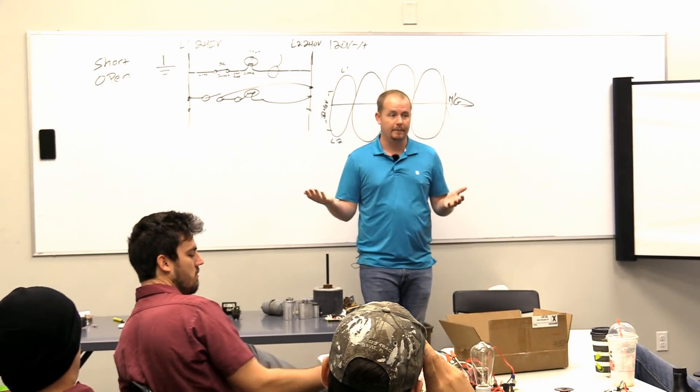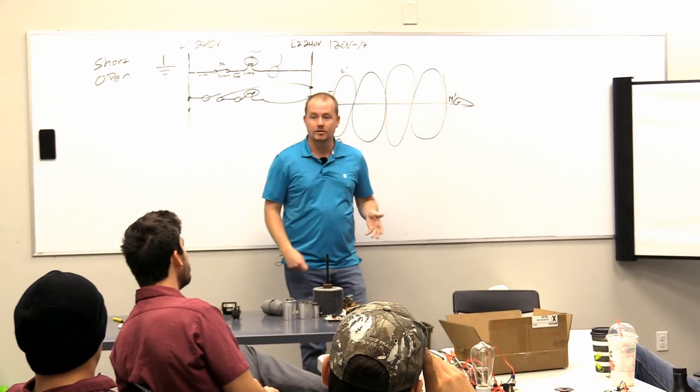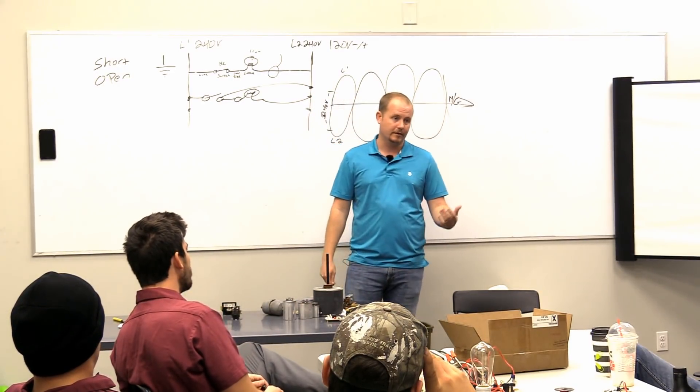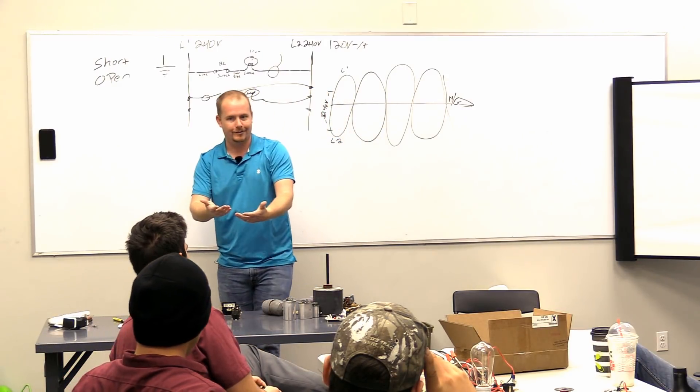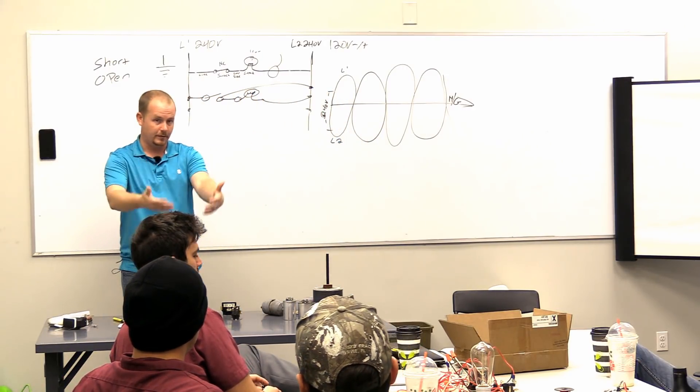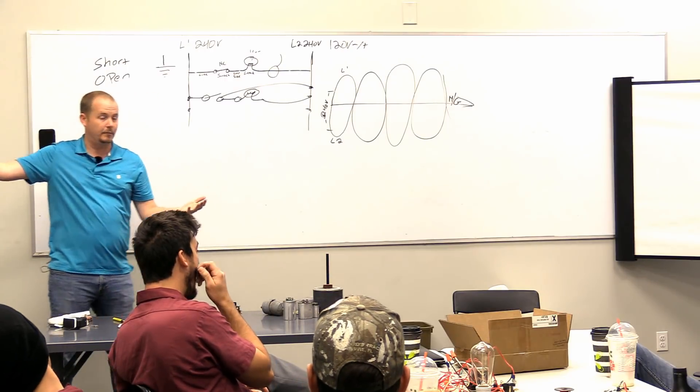And we see guys do this from time to time. They walk up and they got a hose on the compressor. What are you doing? Well, I think it's shorted. I'm trying to reset it. It's like, no. Open overload results in an open circuit compressor not running, but not resulting in a breaker tripping.